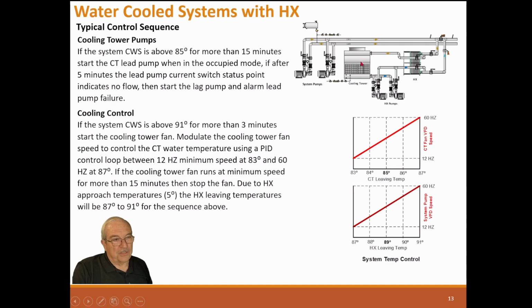85 degrees is just a standard temperature, but the heat pump system or an air-cooled or water-cooled system will run down at 75 degrees, no problem, or 80 degrees. So if you have colder temperatures, say it's not the hottest part of the year, you can drop these down and have it run at a colder temperature. It just runs the fan a little longer. So I've set these the highest that would be amenable, but you could actually set these lower.